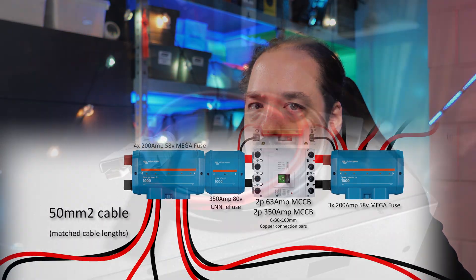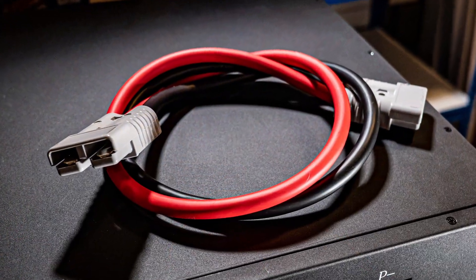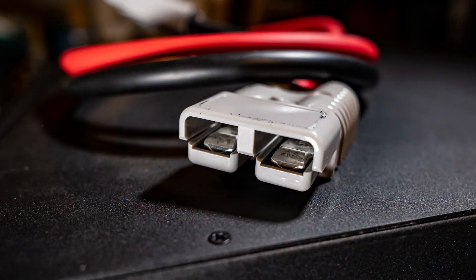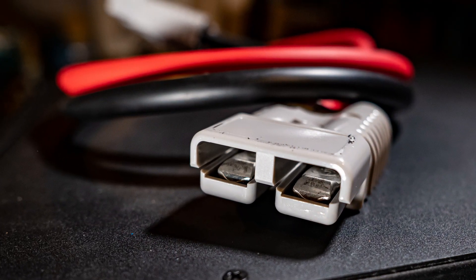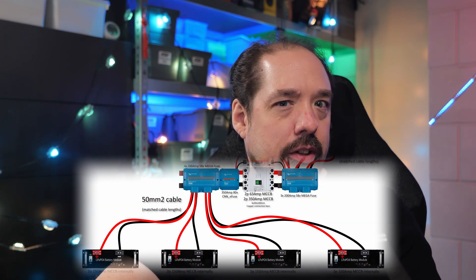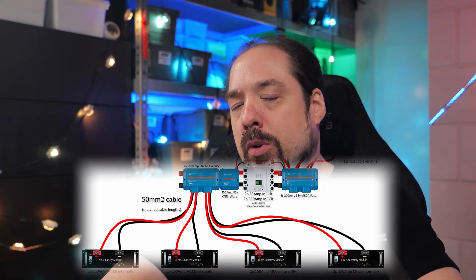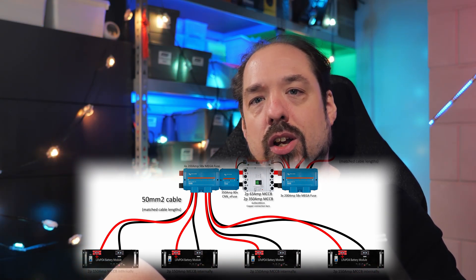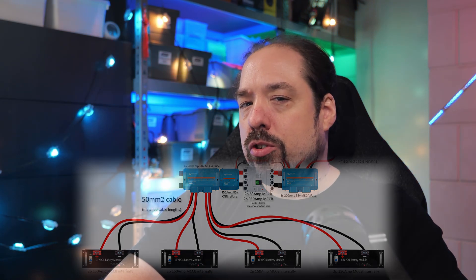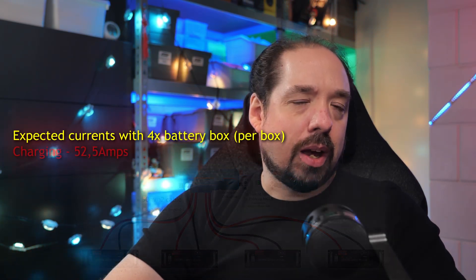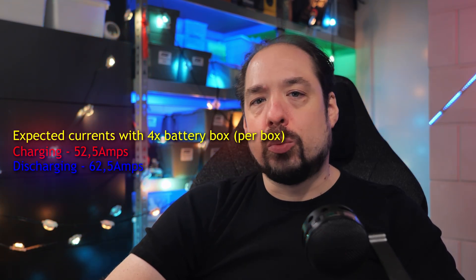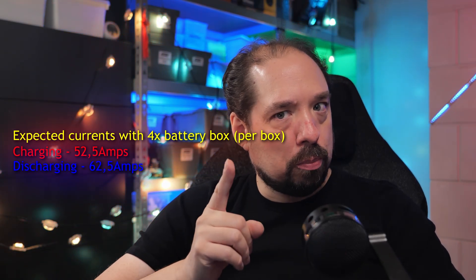Now, we're using 50 millimeter square or zero gauge cable from the battery boxes to the Lynx Power In. These cables should easily suffice up to 150 amps, but once all boxes are completed, the maximum expected current are much lower than that. When all four batteries are live, we won't see more than about 50 amps when charging or 62.5 amps while discharging per box.